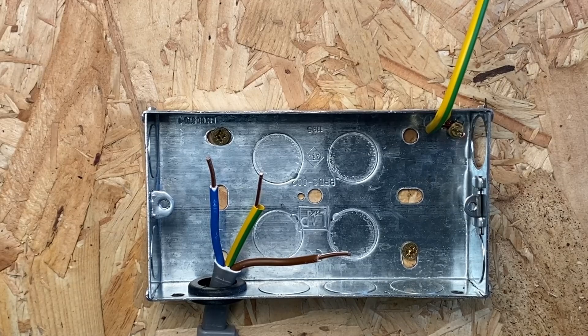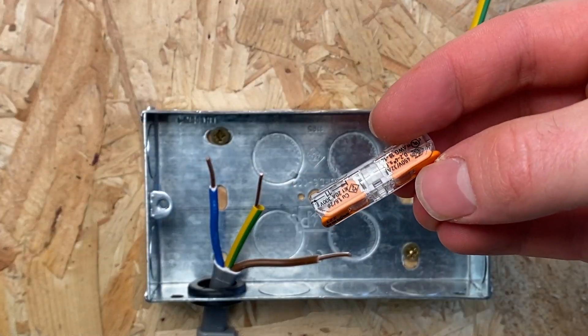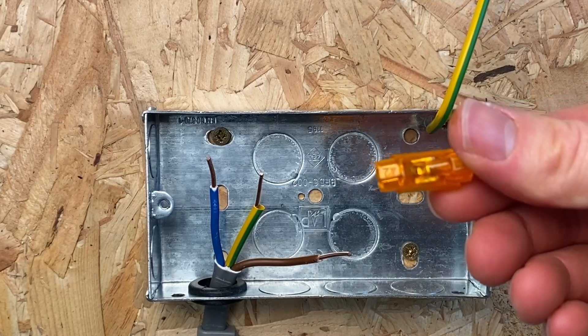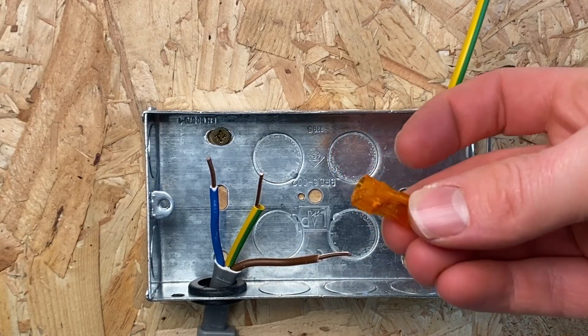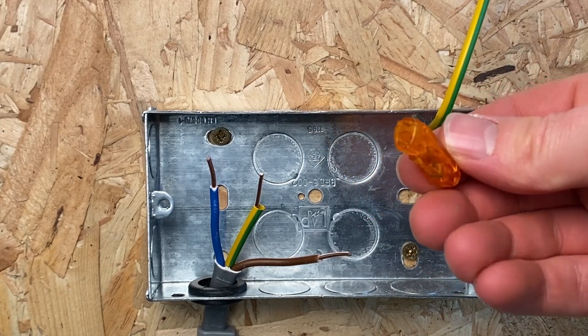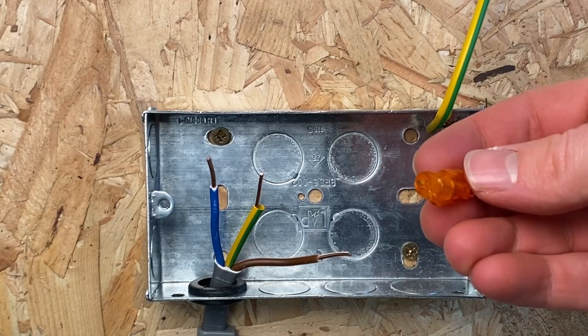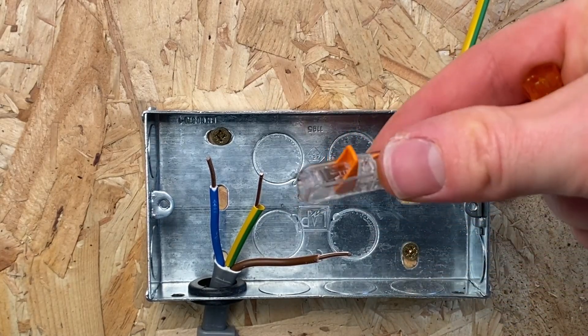The next option is a Wago straight line connector - personally I think this is the best option. Another good option is one of these Ideal inline connector. These are just push-on. The difference with the Wago is that it has a lever so you can undo it, whereas this one does not have a lever, so once it's on it requires quite a bit of force to remove it. The Wago you can just lever up to undo.